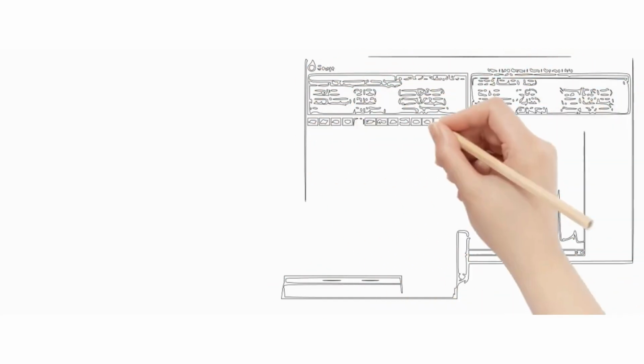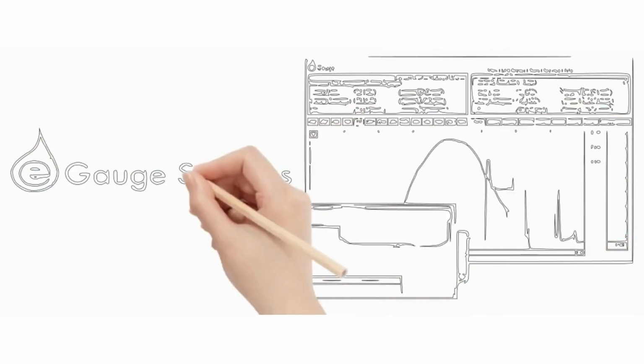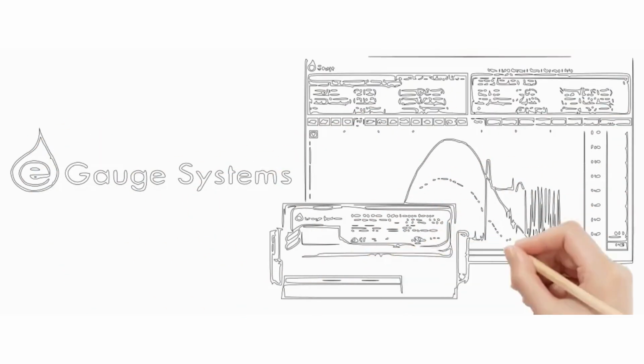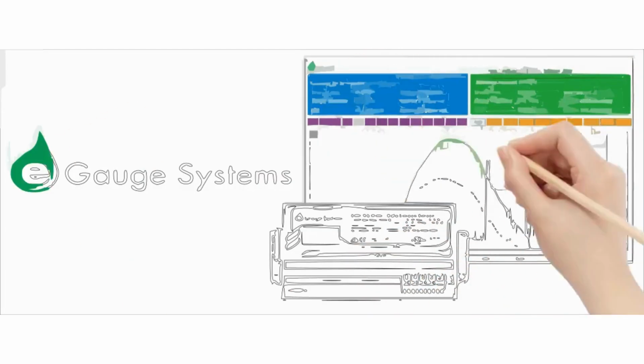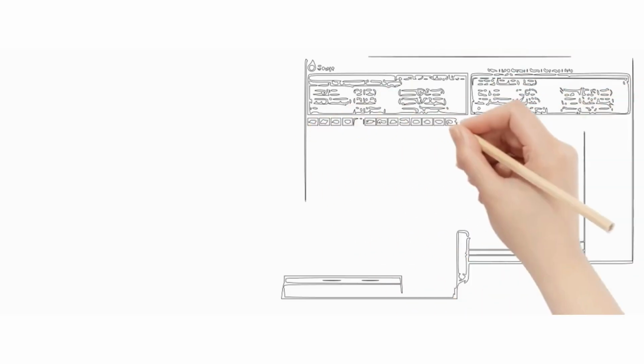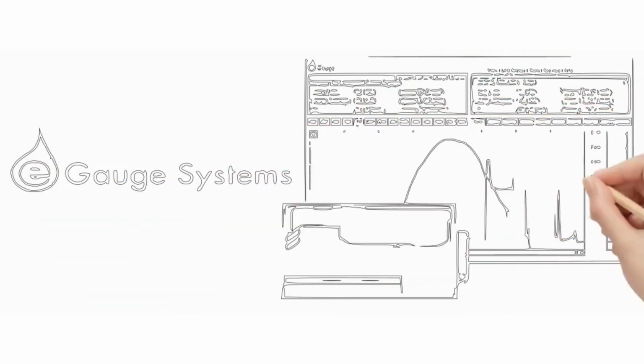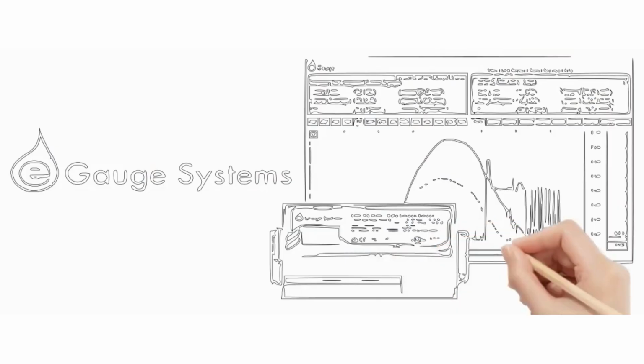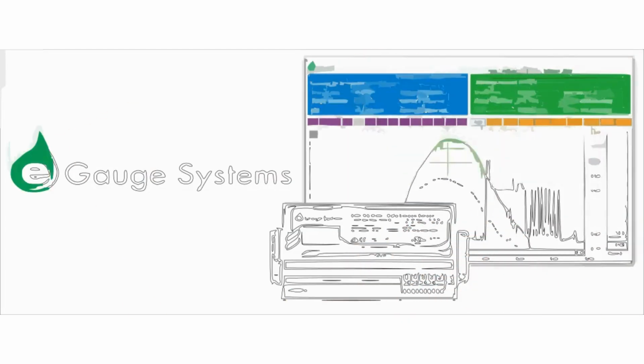The big one is real power, often shown as P, calculated as P equals V times I times the cosine of the phase angle. You need that precise phase angle, which comes from the synchronized sampling, to get the cosine part right. That tells you your power factor, how efficiently you're using the power delivered. Without sync, you're just guessing.